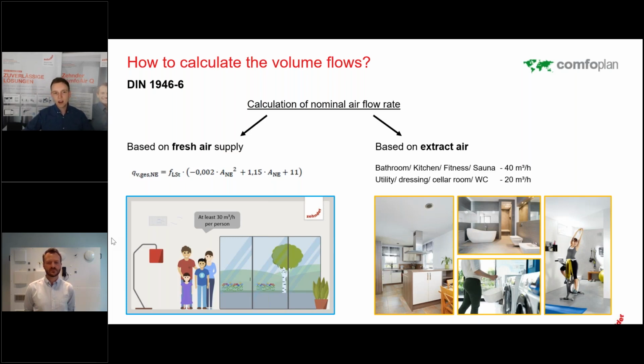You can see the area is not considered extract air. It is assumed that the loads are equal in every bathroom, for example. So it's not a matter of the size of the room. You also can adapt this to a certain level, so you have factors to weight the rooms differently. At the end, the higher volume flow is chosen and the smaller one is adapted to the other one, so that the system is in a balance at the end.